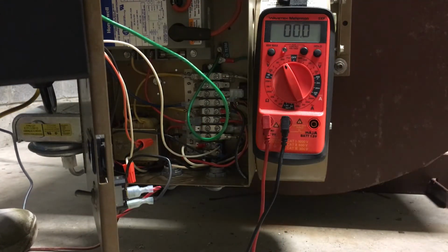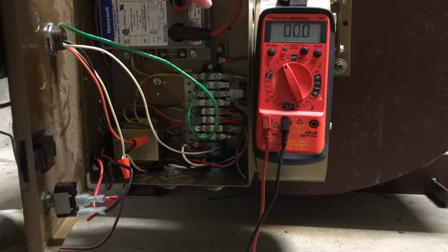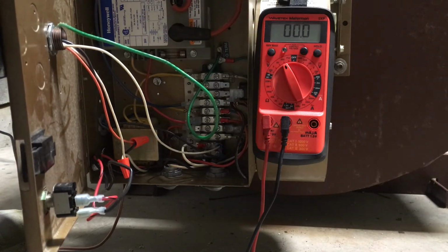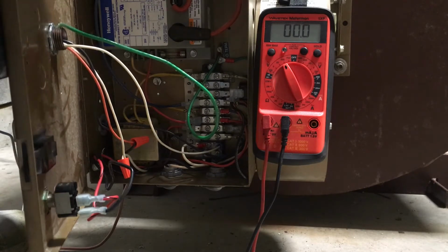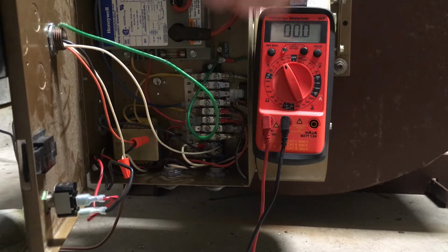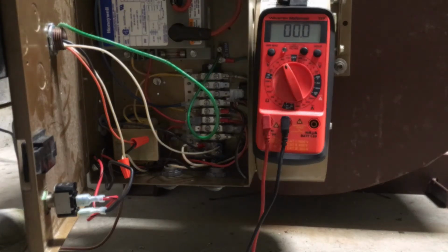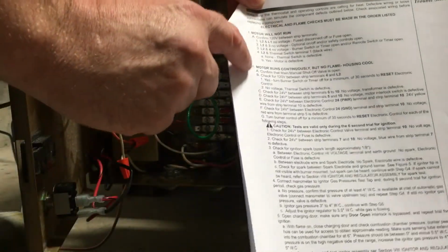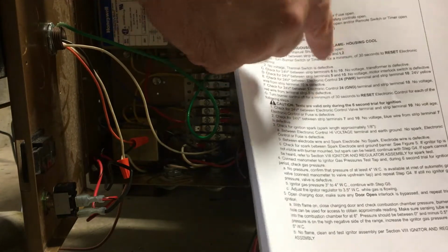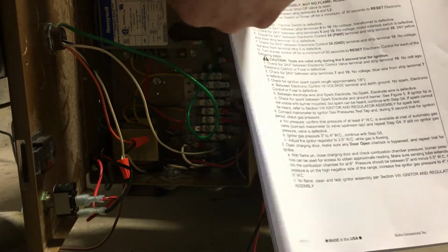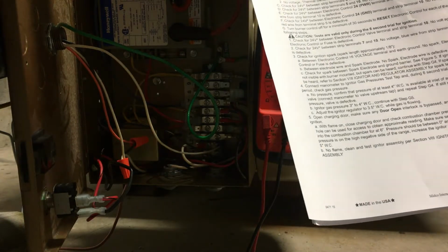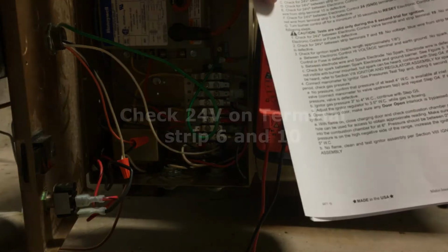Now that we have checked for proper line voltage, your incoming voltage of 115, 120 volt, we're going to go through and verify all the other switches work properly, whether it be your air proving switch, your interlock switch, anything that's more or less 24 volt. As we go to the next step on the troubleshooting chart: if your motor runs continuously but no flame, or the housing is cool. That means the motor is operating, but we're not getting any flame, any burn. So we're going to go through the steps here. As we verify steps 2A and B, we have already verified the thermal switch in the previous steps, so we know that it's properly working. So we're going to go on to the next steps.